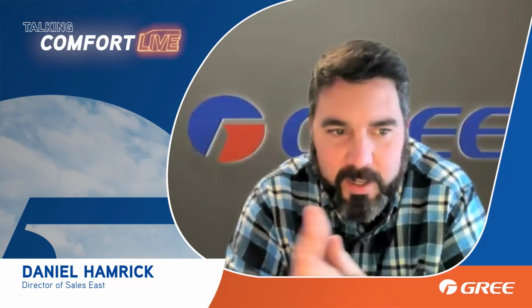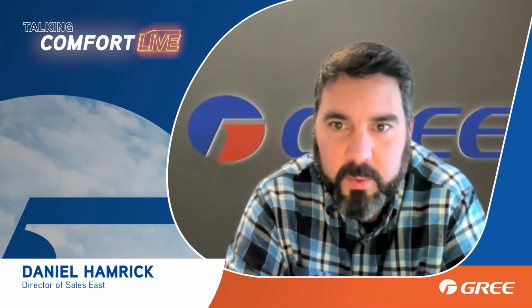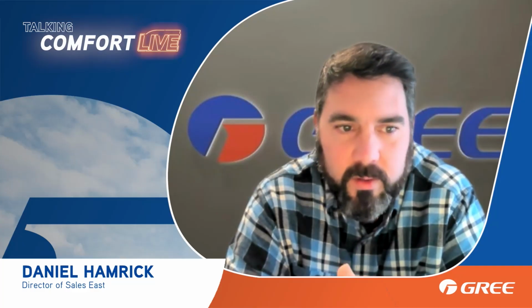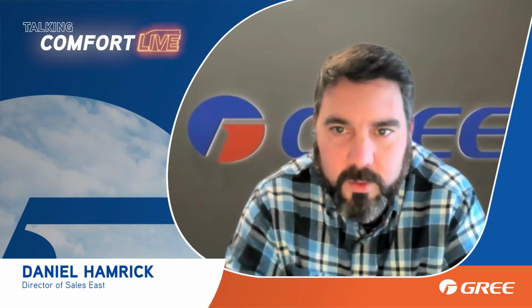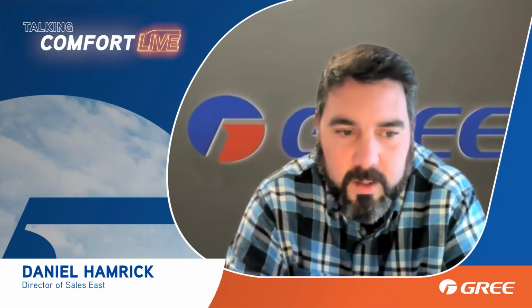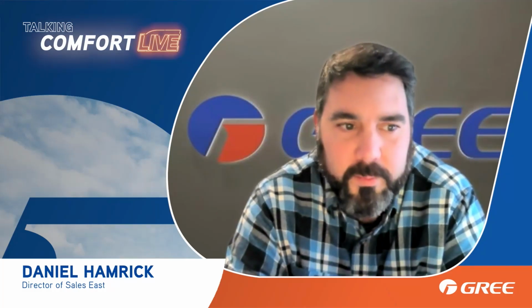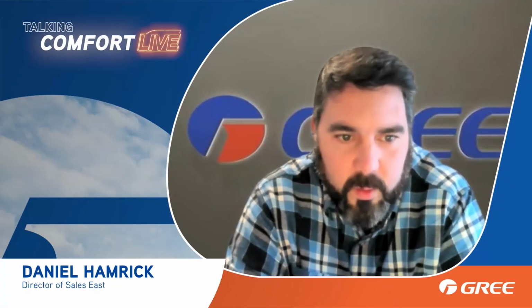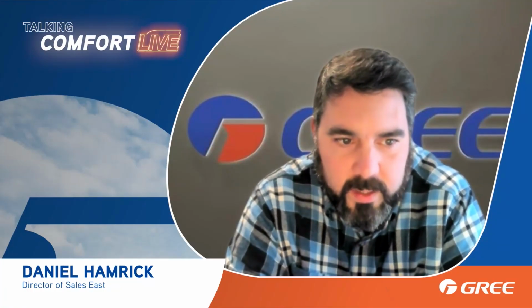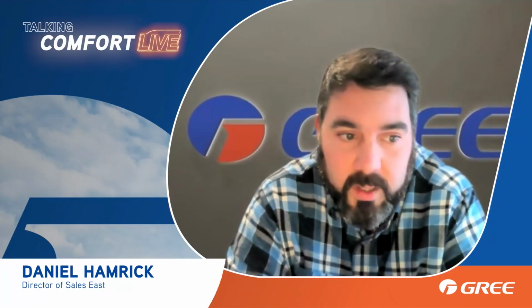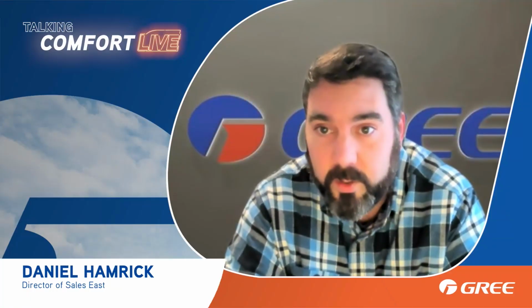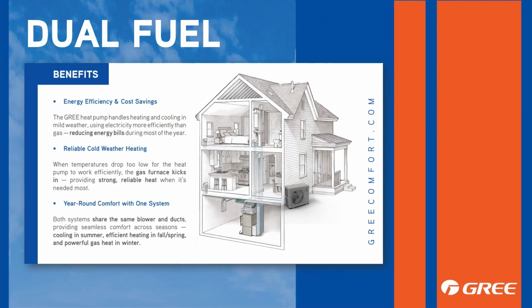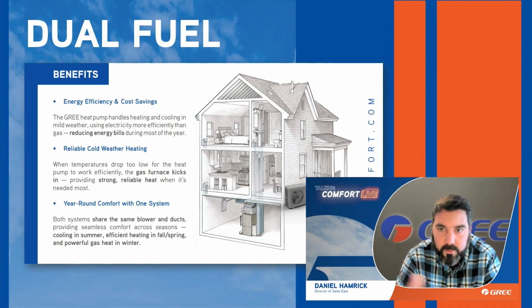Well, of course. So basically, dual fuel is when you take a heat pump and install it with a furnace and an indoor coil, so you have essentially two sources of fuel: electric heat pump and gas or whatever. You've got the GREE outdoor heat pump matched with an indoor gas furnace. The idea is to take advantage of the efficiency of the heat pump as it handles nearly all of your comfort needs, especially a GREE one, because they can heat down to -22 in all four seasons, with the option to automatically switch over to an alternative heating source, being the gas furnace, during times of extreme or sustained cold. And a lot of that has to do with balance point, which we'll talk about a little later.